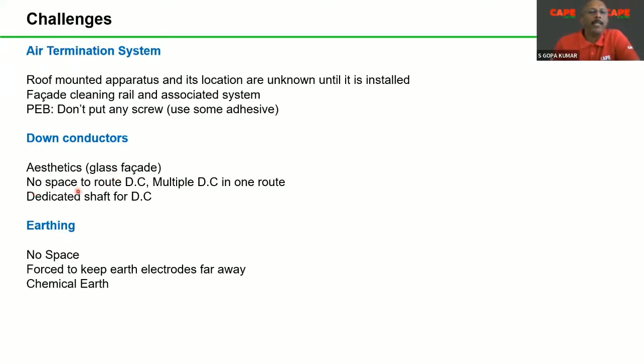The second case, there is no space to route down conductor. Third case, multiple down conductors in one route. All these are actually violation of the standard. And then in some cases, architects are providing a dedicated shaft for down conductor. So I have 3 down conductors. You require 15 down conductors, and all the 15 down conductors as group of 5, you take through 3 shaft. That is also not possible.